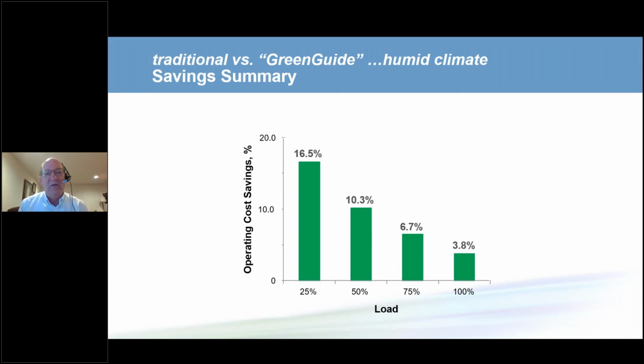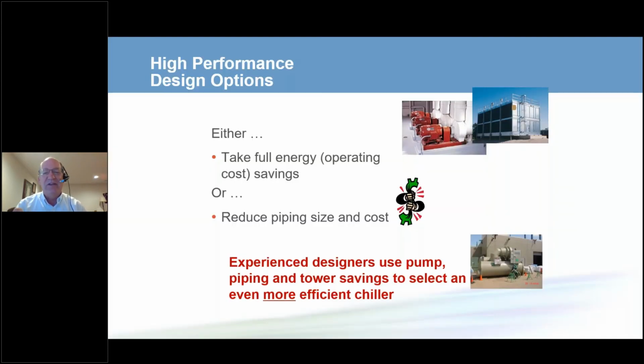And that's a great benefit, and that's why the ASHRAE GreenGuide, ASHRAE Standard 90.1, the Advanced Energy Design Guides, and the chilled water design course from ASHRAE tell us to reduce the flow rates, because it saves energy from a system standpoint. Now, as a consulting engineer, as a building owner, as a contractor, you now have some decisions to make. As I stated before, the assumption was that we left the pipe sizes the same. When we leave the pipe sizes the same, the pump power goes down by a lot, and therefore the pump energy goes down by a lot.